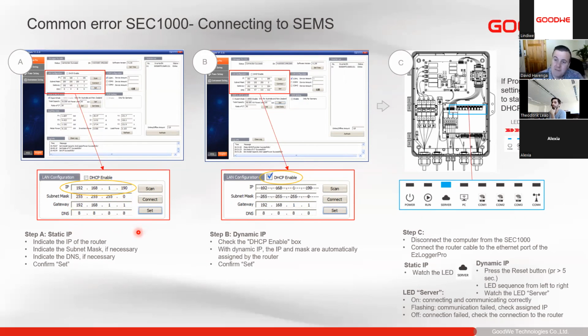The nice thing of having a static IP address is that you can always access it on the customer's network again. So if you do set this up, take a pen or Koki and write on the cover the IP address of the logger. So if you come there in future, you don't have to reset anything, you just connect to the network and then you can log into the logger via ProMate and configure it.